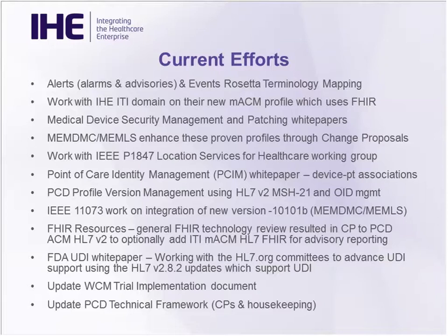Plus, the information can be used in device efficiency and effectiveness monitoring, so that if you know all the times a device is associated with a patient, you know it's being utilized. Knowing how the device is utilized can also lead to better management of the maintenance of the device, so that you don't have a calendar-based static cycling of maintenance on the device. You have device usage-based maintenance.